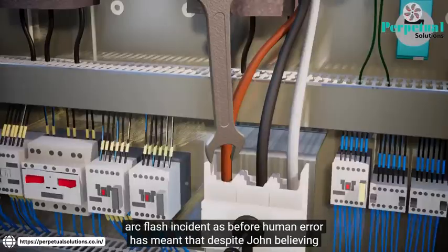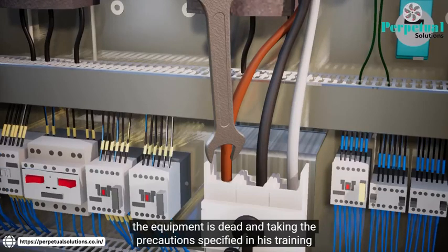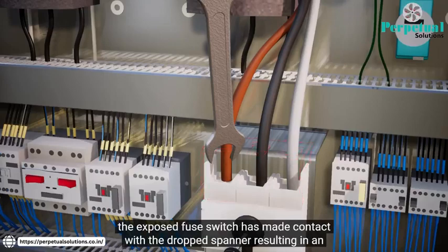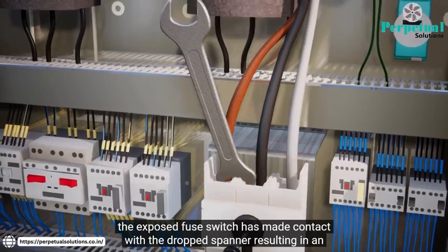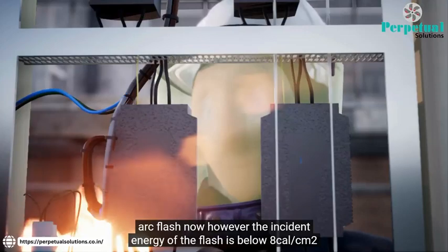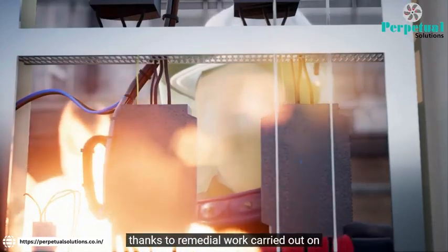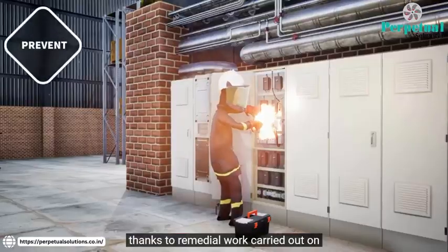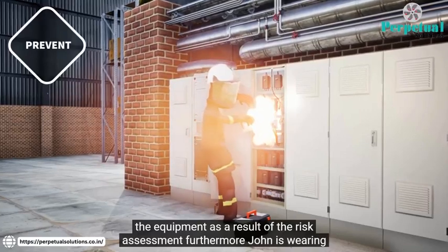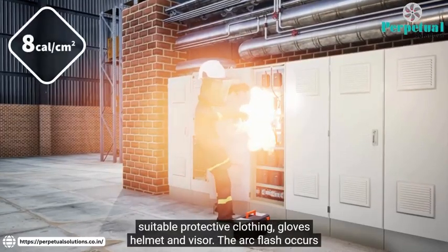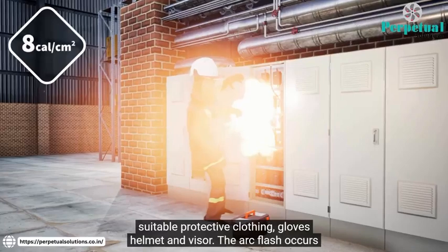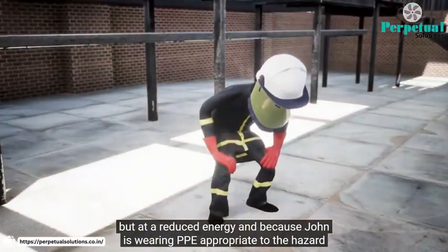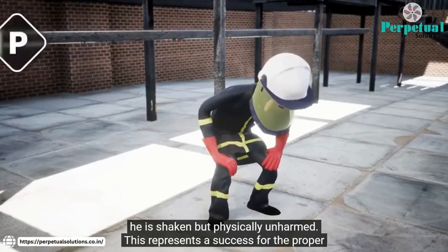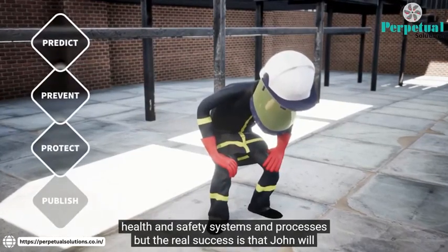Now let's return to the arc flash incident. As before, human error has meant that despite John believing the equipment is dead and taking the precautions specified in his training, the exposed fuse switch has made contact with the dropped spanner, resulting in an arc flash. Now, however, the incident energy of the flash is below 8 calories per square centimetre, thanks to remedial work carried out on the equipment as a result of the risk assessment. Furthermore, John is wearing suitable protective clothing, gloves, helmet and visor. The arc flash occurs, but at a reduced energy, and because John is wearing PPE appropriate to the hazard, he is shaken but physically unharmed. This represents a success for the proper health and safety systems and processes.